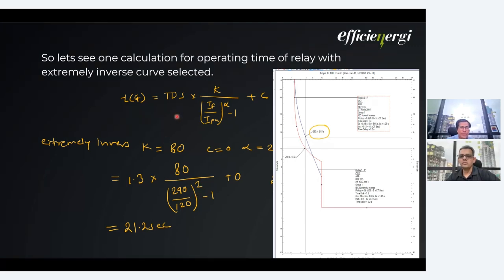Here, with the example of this equation given as per the IEC, we are just trying to calculate. For extremely inverse, the value of constant k is 80, c is 0, and alpha is 2. With the same curve, we are considering 290. We want to find the tripping time for 290 ampere, and we are setting this curve with a set value of 120. So the fault current is 290 and the set value is 120. If we calculate with this alpha and this C, it comes to around 21.2 seconds. So for extremely inverse, we are getting 21.5 seconds on the TCC.